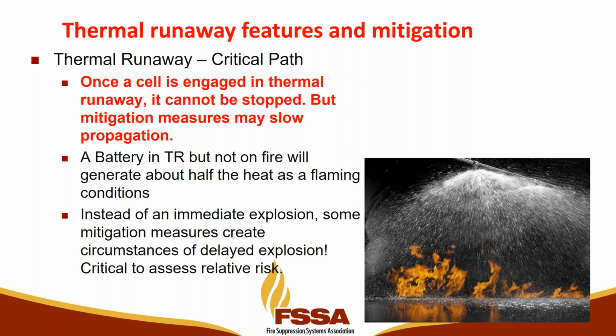So once a cell is engaged in thermal runaway, it cannot be stopped, but hopefully we can put in mitigation measures that slow the propagation and keep it a little more under control. A battery in thermal runaway, but not on fire, will generate about half the heat of a flaming condition. When they're burning, we've seen about 1,000 degrees C. When they're not burning, they still propagate at about 400 degrees C. So sometimes you're not going to see an immediate explosion, but you may create circumstances where you have a delayed explosion.